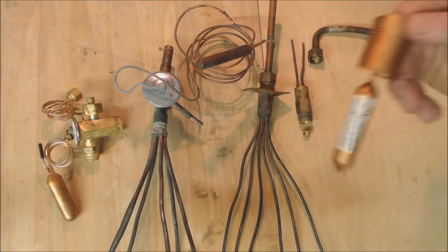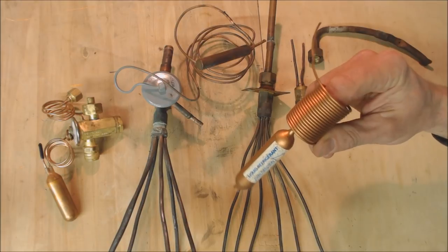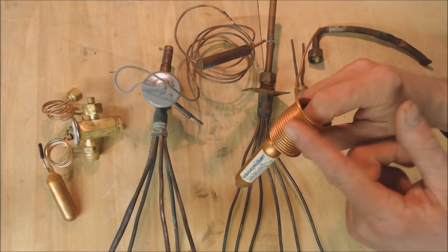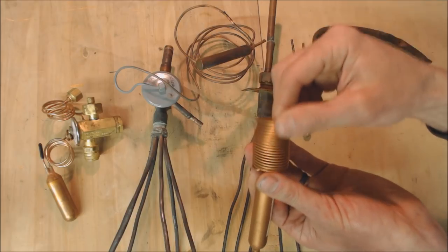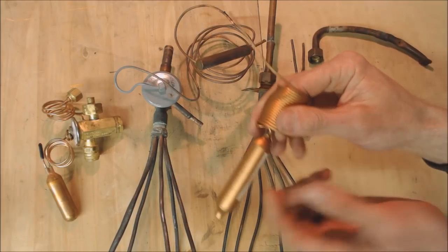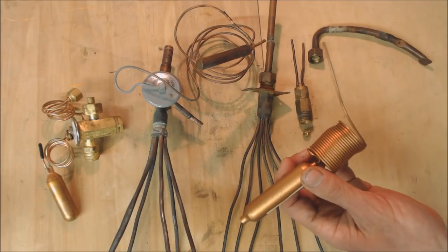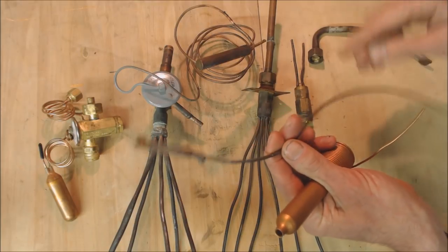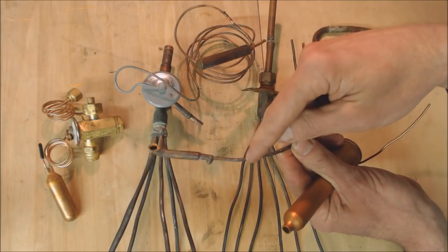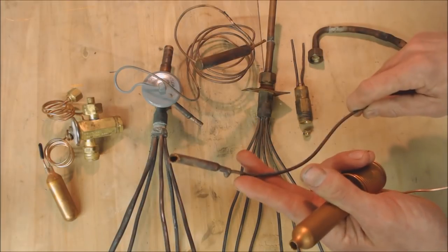This also falls in the category of a fixed orifice, and this is capillary tube. This has a set inside diameter and also a set length by the manufacturer. You may or may not see a strainer on it. It may just come right from the tube into the capillary tube and then right back out the other side into another line.